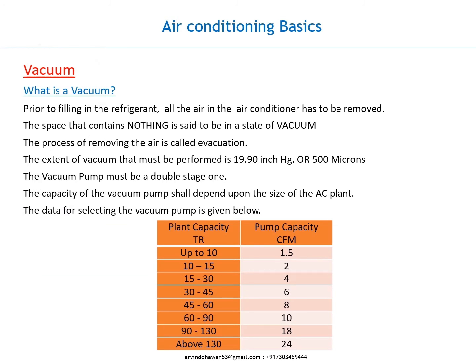What is a vacuum? Prior to filling in the refrigerant, all the air in the air conditioner has to be removed. The space that contains nothing is said to be in a state of vacuum. The process of removing the air is called evacuation. The extent of vacuum that must be performed is 19.90 inch HG or 500 microns. The vacuum pump must be a double-stage one; its capacity shall depend upon the size of the AC plant.